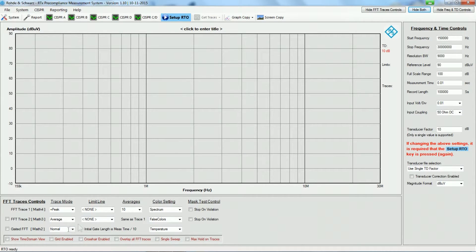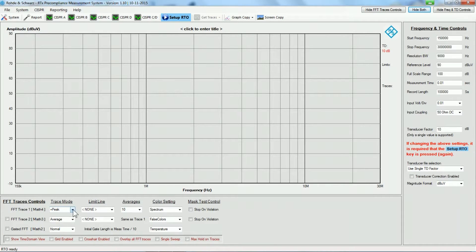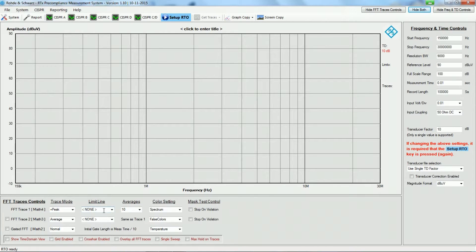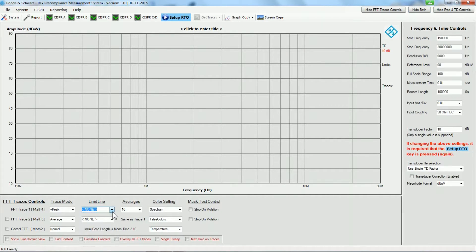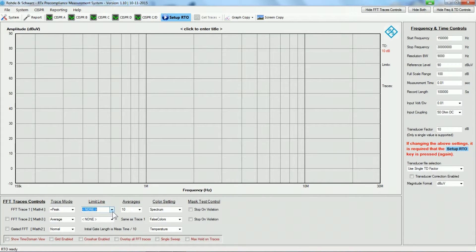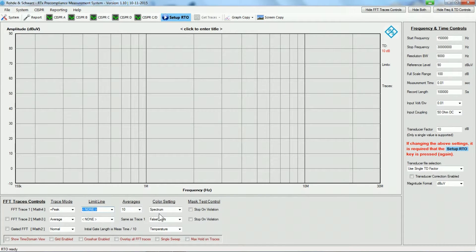What do we want? Do we want peak detector? Do we want average detector? And so on. We can set up limit lines so that we get measurement results presented in a way that is very similar to what we are getting on spectrum analyzer measurements.